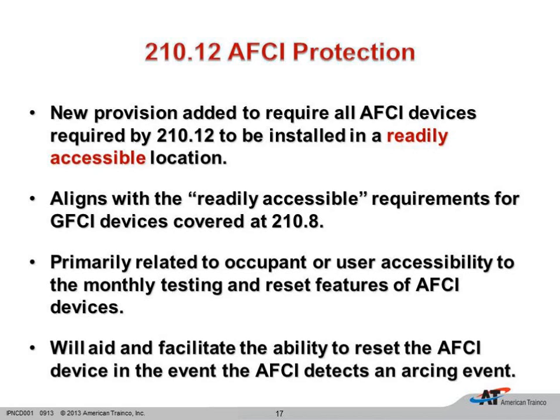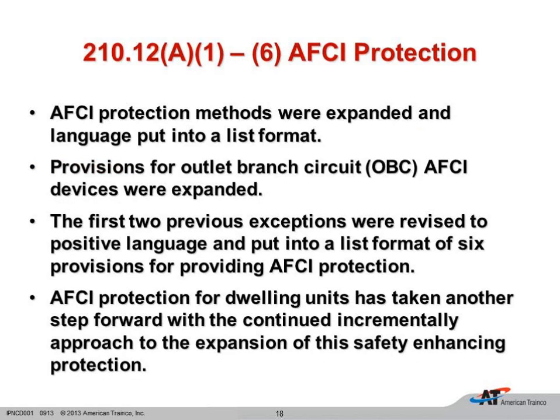So we have to remember this. They have to be readily accessible, so that these AFCIs are going to be able to, they have the same testing requirements as a GFCI. So every month we're going to have to go up and make sure that they're operating properly. And those 6 choices are put into a list in 210.12, and they're calling the receptacle an outlet branch circuit device. And so we have a lot more opportunities, I guess, to provide protection for homeowners in the case that there is some arcing going on behind those walls.